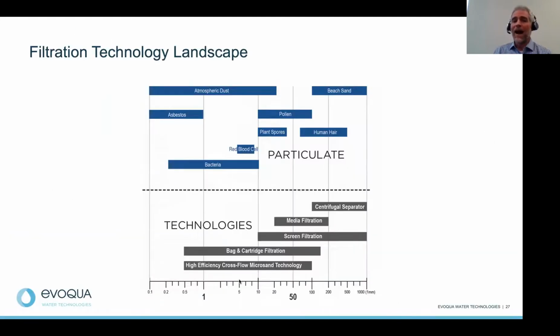The Vortisand is a high efficiency media filter that really focuses on the lowest end of the spectrum of particulate filtration. We talked about centrifugal separators, 100 micron nominal. Screen filters, around 10 microns. And now you're getting into the point where you're able to compete with bag and cartridge filters, but now you're able to do that at an automated capability. You're able to get down to sub-micron performance, less than 1, down to half a micron, in an environment where you're automatically self-cleaning that product.